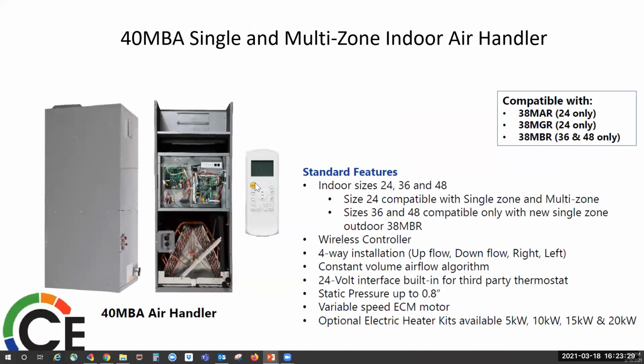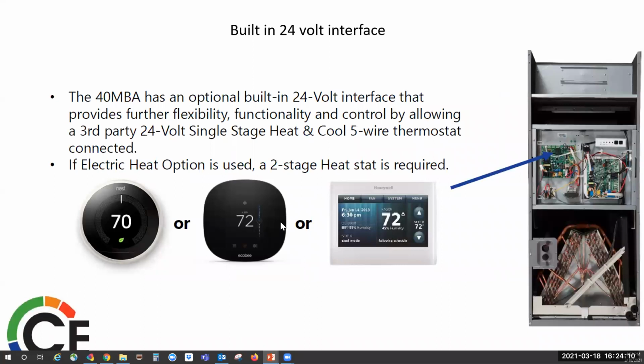The 40 MBA single multi-zone indoor air handler. It is only compatible with 38 MGR, 38 MAR, and 38 MBR, depending on the size. We have constant airflow, constant airflow algorithm, built-in 24-volt interface, so you can use a 24-volt thermostat. Once again, wireless remote control. You will use this wireless remote control to set static pressures. Once again, we do have the built-in 24-volt interface.